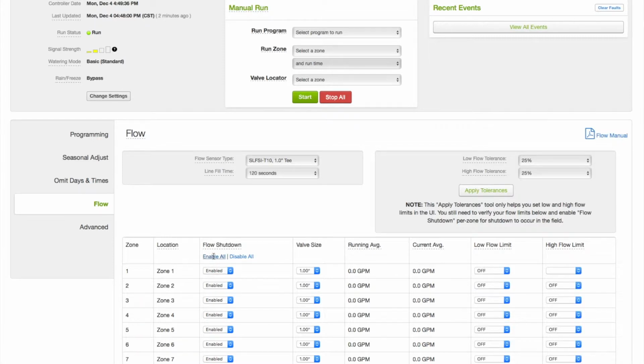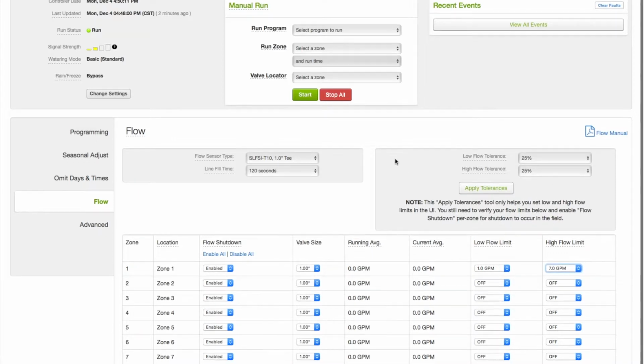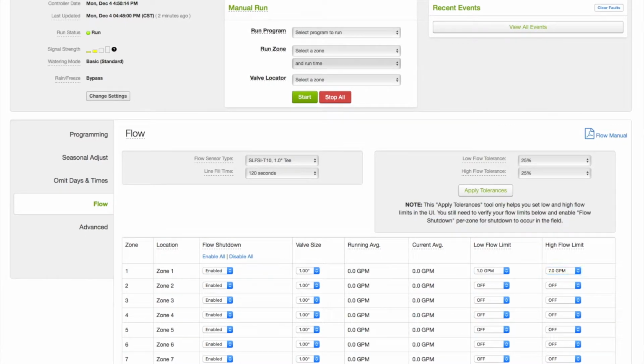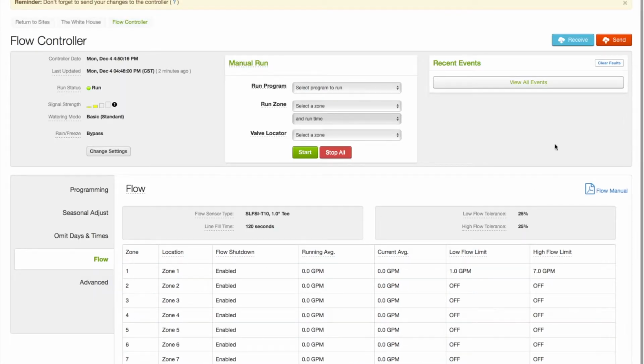You can enable them all. You can also custom set the thresholds without applying the tolerance. Keep in mind, if you set this low flow tolerance at 25% and the flow is a low flow zone, you may have to increase the threshold higher than 3 or 4 gallons a minute in range. If not, you could have a lot of nuisance faults. So we'll save these changes and send them to our controller.